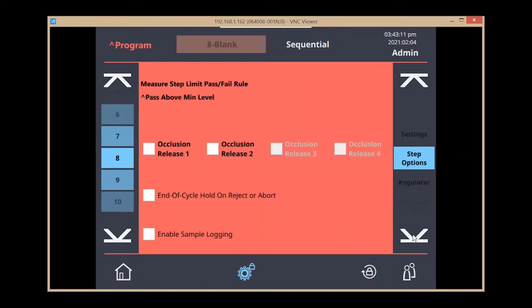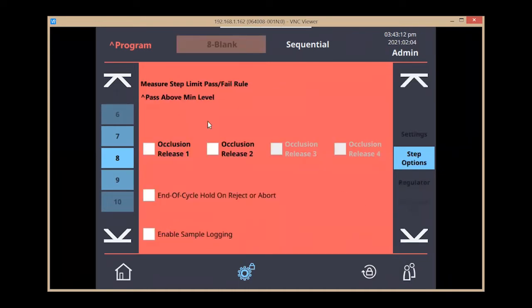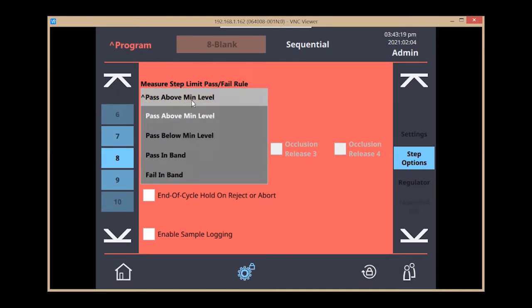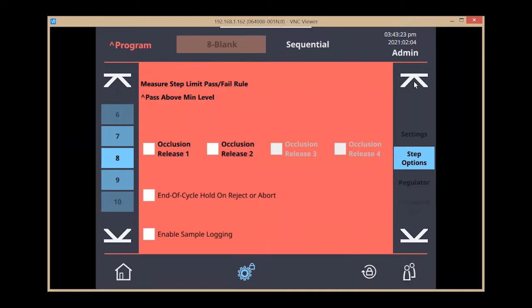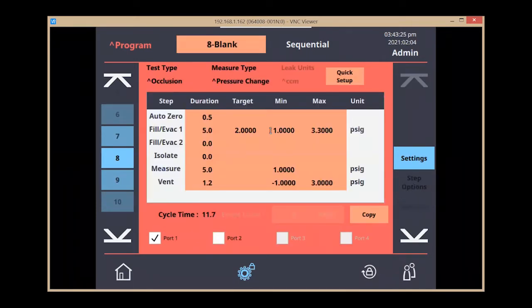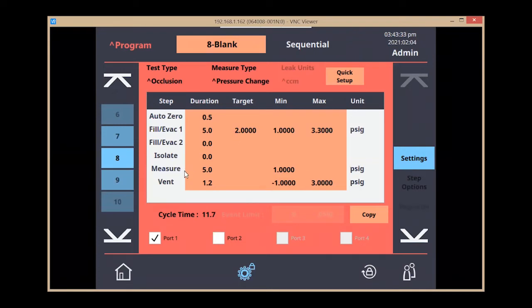If I go to my step setup menu, I'm going to look for the measure step limit pass-fail that pass above the min limit. For today, the way our program is going to work is I'm going to fill it for five seconds to a target of two psi, and then it's going to move on to the measurement step and look for a pressure drop of one psi.